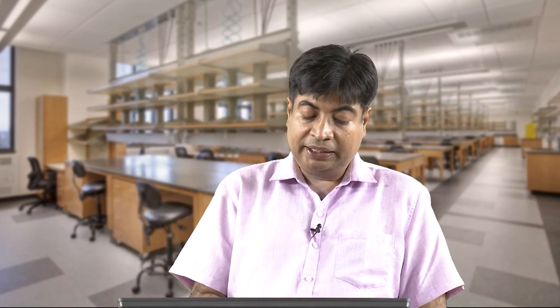Let us come to another version called hybrid topology. We can have a shunt active power filter with switches and hybrid power topologies. Ultimately, the shunt active power filter may compensate the higher-order harmonics, because you can tune passive filters to the fifth and seventh harmonics, and concentrate the active filter on higher-order harmonics so that the rating of the active filter devices is less. By strategically placing passive and active filters and deciding which one concentrates on which harmonic, you can reduce total harmonic content and obtain an optimized solution for the system.